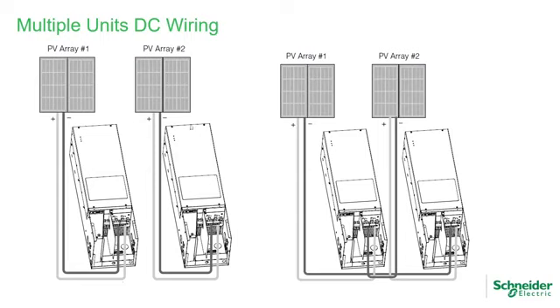And what I'm showing you here is this mistake is probably one of the most difficult troubleshooting because the units will operate during commissioning. You will actually have all the checkpoints and everything will check fine. But what will happen is because you have the negative of one array connected to the other charge controller and then the same on the other side, the MPPT, the maximum power point trackers of the two units are going to be fighting each other.